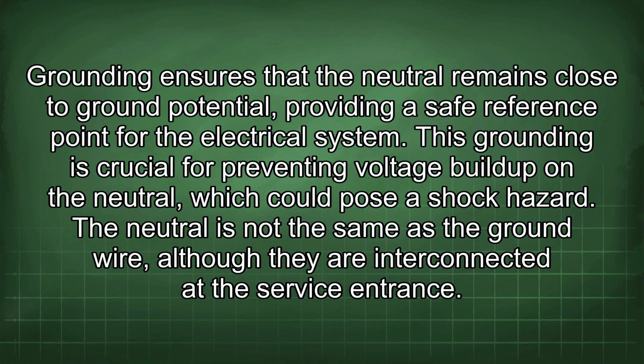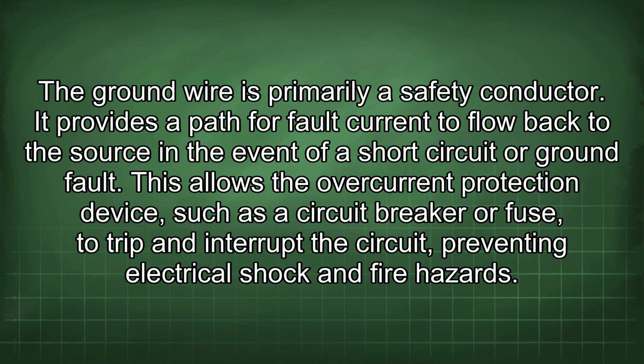The neutral is not the same as the ground wire, although they are interconnected at the service entrance. The ground wire is primarily a safety conductor. It provides a path for fault current to flow back to the source in the event of a short circuit or ground fault. This allows the overcurrent protection device, such as a circuit breaker or fuse, to trip and interrupt the circuit, preventing electrical shock and fire hazards.